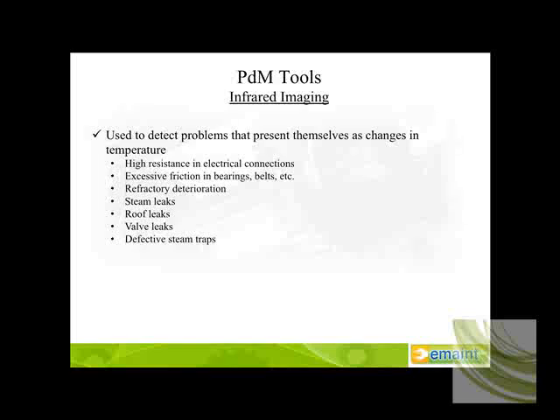A couple of other things to take into consideration when evaluating infrared instruments and implementation of those instruments is that they can be sensitive to external influences. For instance, wind blowing across the surface of any target will convectively cool any temperature that you're looking at there. Reflected light. Within the infrared world of the PdM industry, you'll hear the term emissivity, which I tend to throw out there as East Mississippi. The simple answer: what is emissivity? Emissivity is the amount of infrared energy that any one given target gives off that the infrared camera can see.